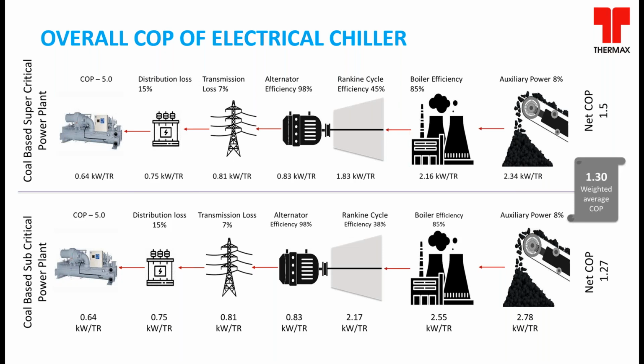To take care of this, the power that has to be produced in the power plant has to be higher than this. Again, in the power plant, there are equipments like the alternator. Again, there is a turbine which will be generating this power, and there is a boiler which generates the steam which is required to run this turbine. So when you take it to the root of this energy production, even with a COP of 5, when you start with 0.64 kilowatt of power per TR of cooling, what we end up is at a number which is much higher than what we started with, which means that we need to burn coal equivalent of 2.34 kilowatt per TR so that the user at the electrical chiller level gets 0.64 kilowatt per TR. So that much is the loss when it passes through all these phases.